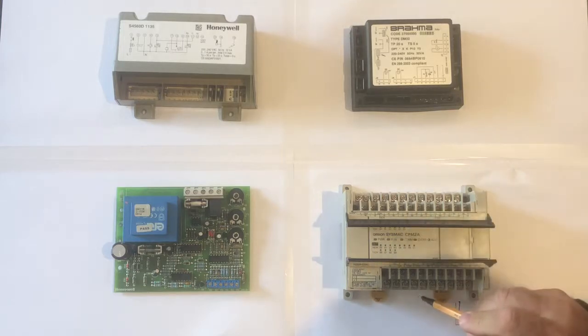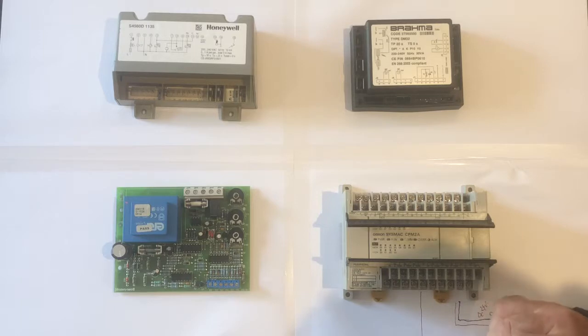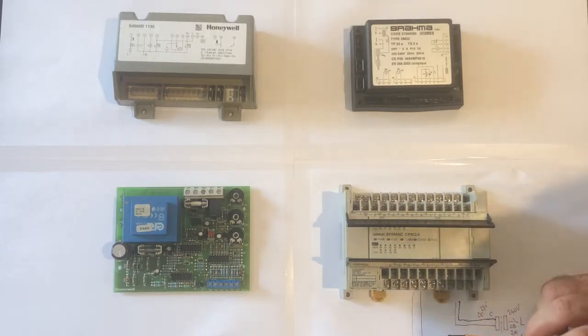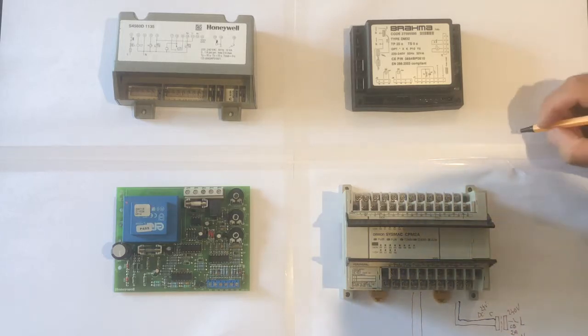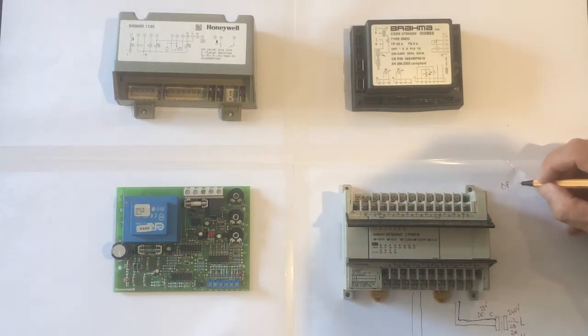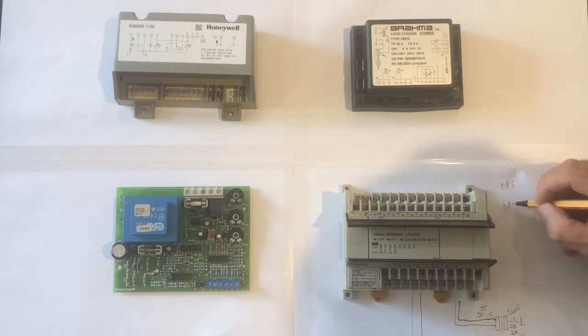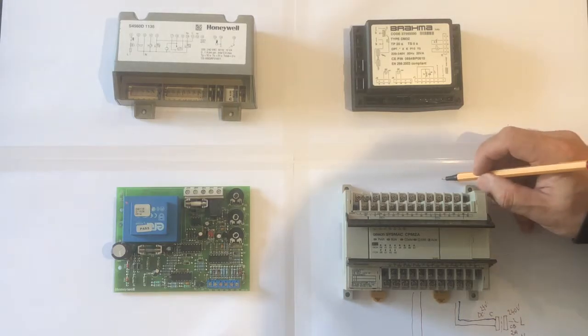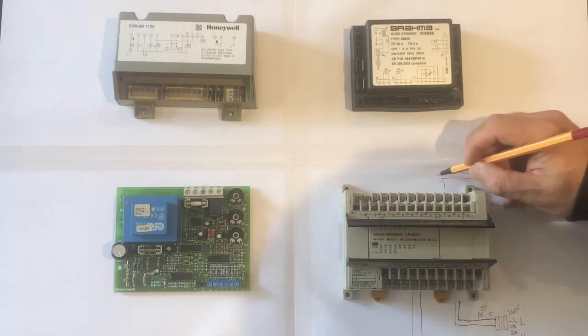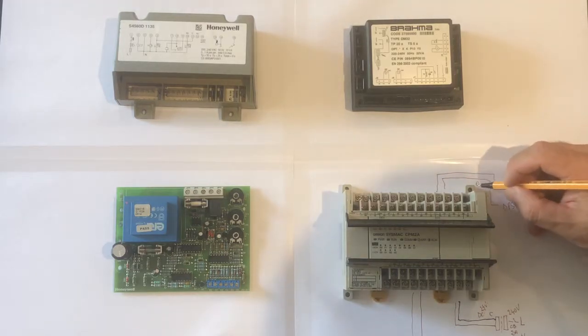The first thing to do: this unit will supply power to a supply fan, SF, then to the extractor fan, EF, which is a fan as well. And then the DPS of the supply fan and extractor fan will send the information back into the BMS, which in our case is the PLC. So it will say okay, they both okay.